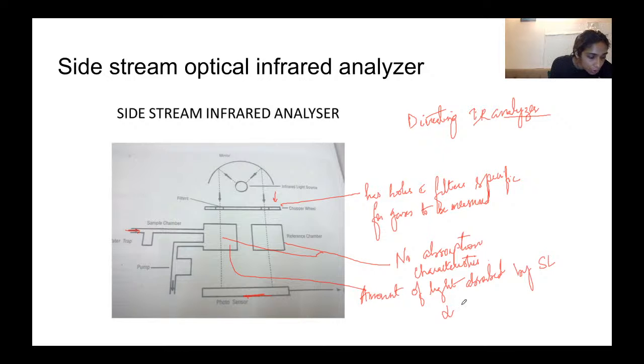So it is directly proportional to the partial pressure of gases whose infrared light absorption patterns correspond to the filter in the wheel. The amount of light absorbed by this sample gas will be directly proportional to the partial pressure of the gas that is absorbed by this wheel, the gas that is basically the filter kept here. Okay, you all got it?